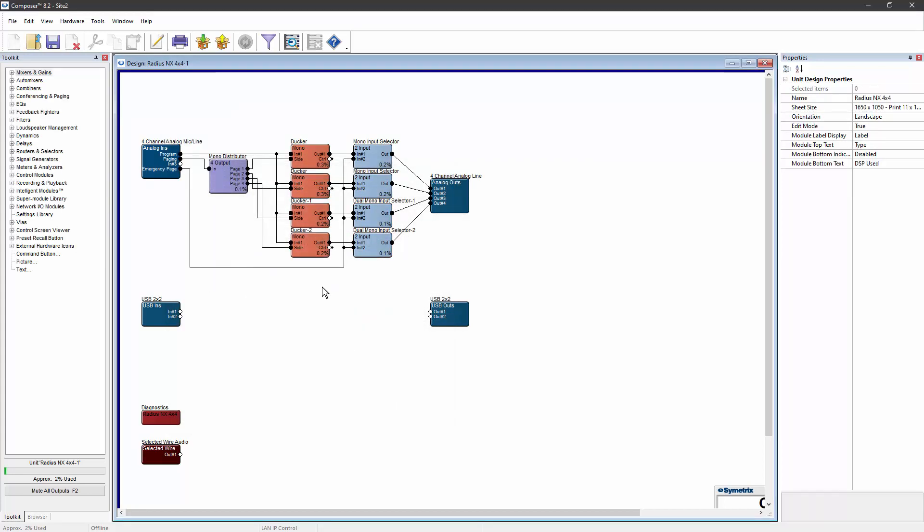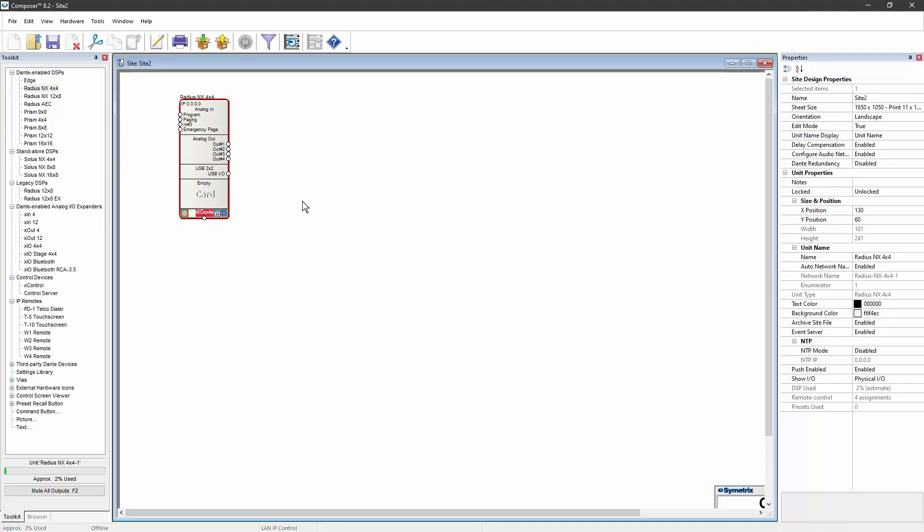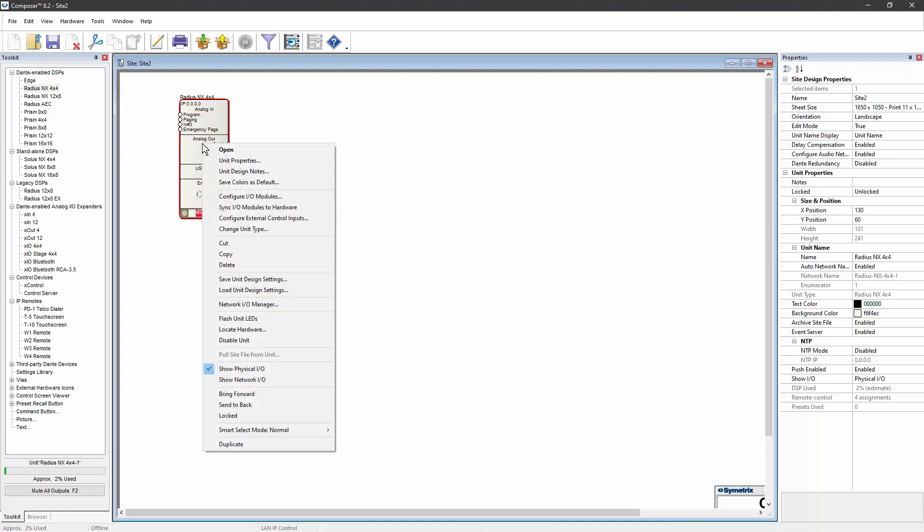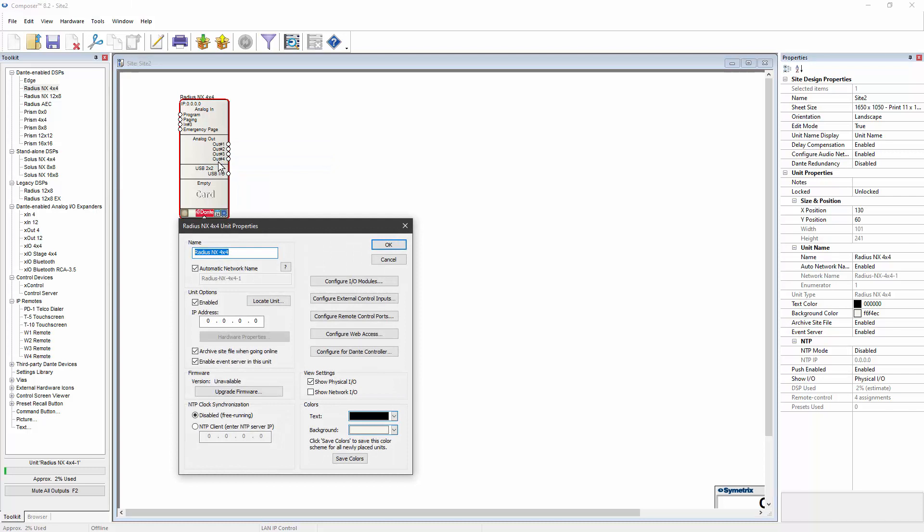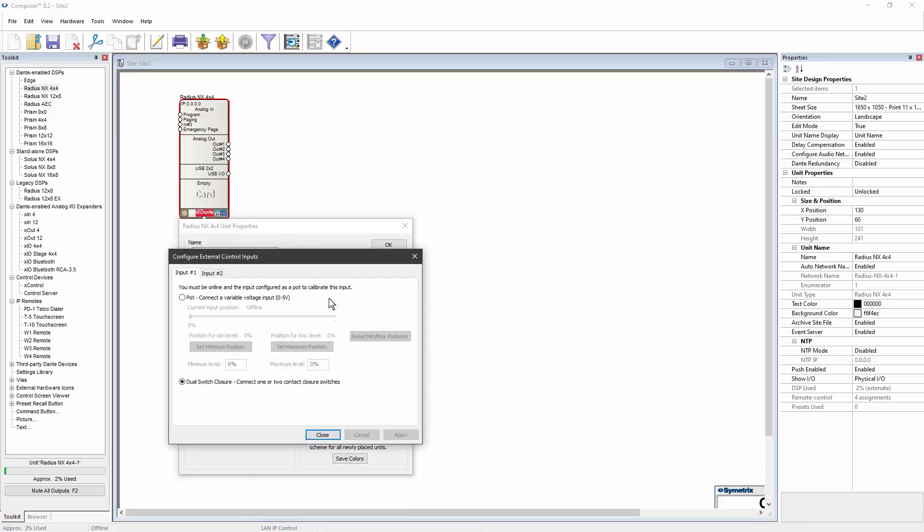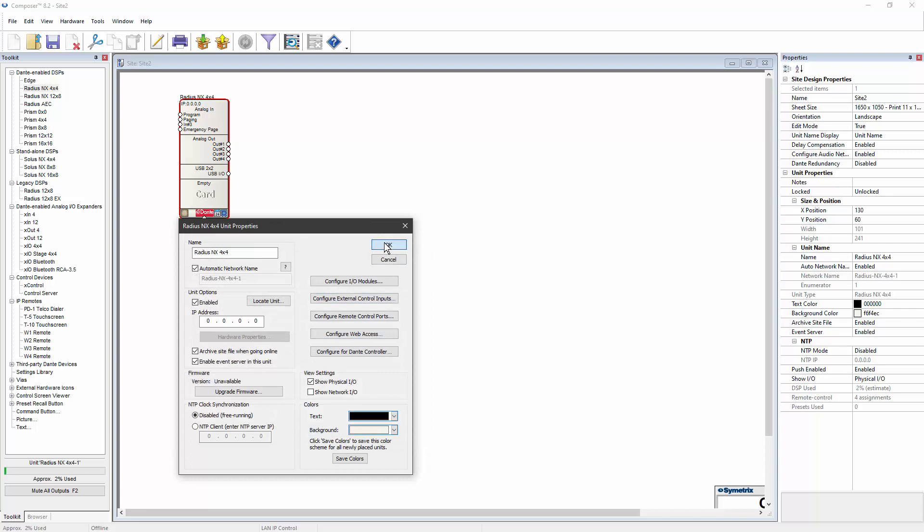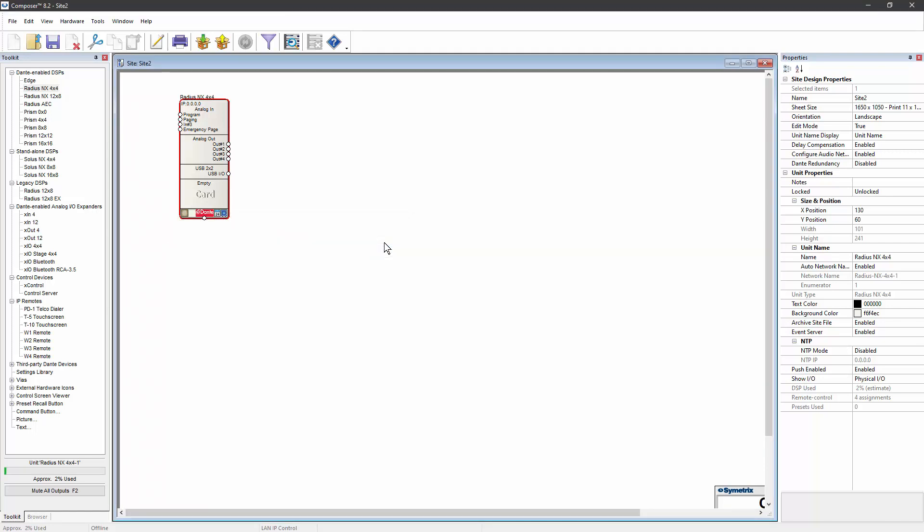The next step would normally be to tie all of those input selectors to a control input that's wired to the fire alarm panel or the emergency annunciator. To do that, first we need to go back to the site view, right-click on our DSP, go to unit properties, and then click on configure external control inputs. In order for this to work, the control input needs to believe that we're connecting to a potentiometer. So go ahead and select pot for input number one, hit OK, hit OK again.